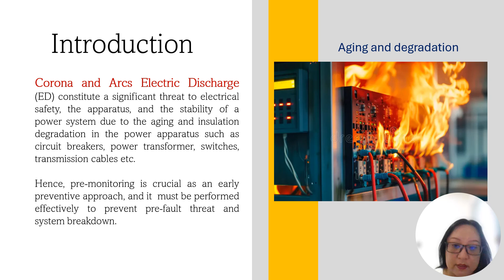Corona and arc electric discharge constitute a significant threat to electrical safety, power apparatus, and the stability of the power system. This is due to aging and insulation degradation in power apparatus such as circuit breakers, power transformers, switches, transmission cables, and so on. Therefore, pre-monitoring is important as an early preventive approach, and it must be performed effectively to prevent pre-fault threats and system breakdown.